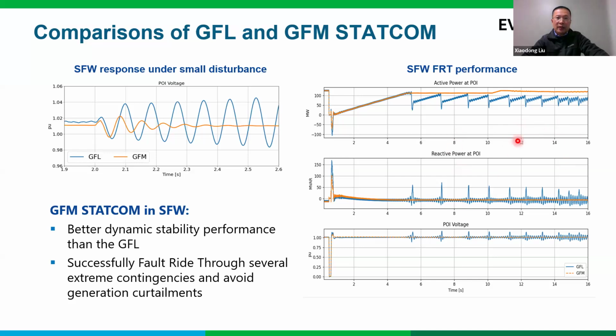The second diagram here on the right shows the fault ride-through under extreme contingency, right? The South Fork Wind cannot ride through the fault under the grid following STATCOM, right? But successfully rides through with the grid forming STATCOM. This improved the stability performance. The grid forming control helped the South Fork Wind avoid many limited operations, that is, avoided generation curtailment in the line outage scenarios when the system is weak.